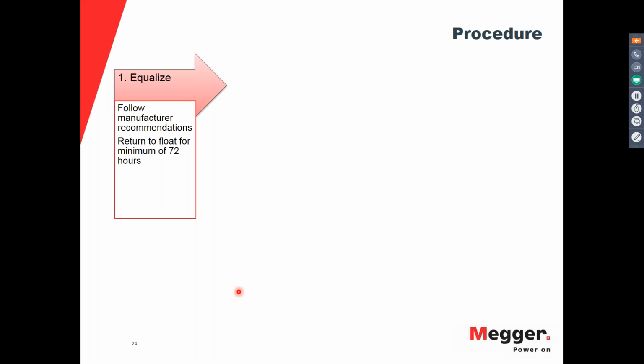And if the battery is equalized, it needs to float for a minimum of 72 hours prior to running the test. This means that if you need to start the test or rerun the test for any reason, then you have to wait for the battery to reach the fully charged condition. And once it reaches that condition, you have to wait 72 hours for it to float, and then you can run the test.